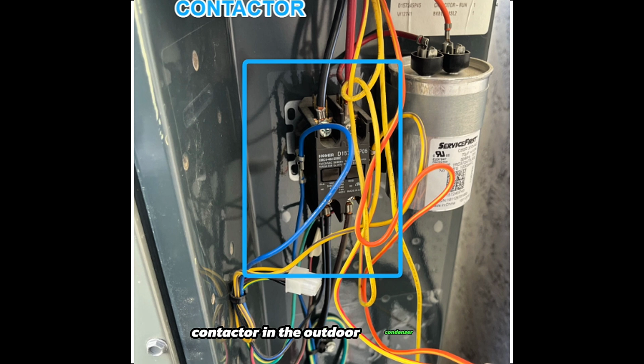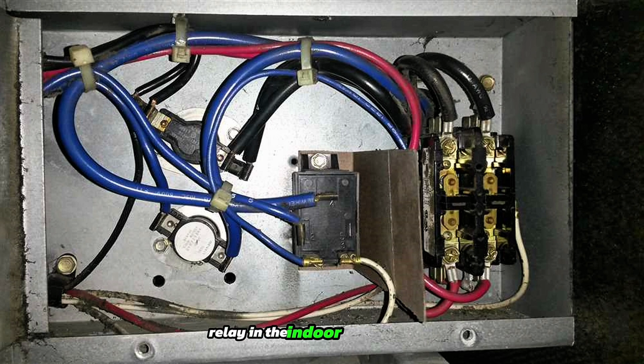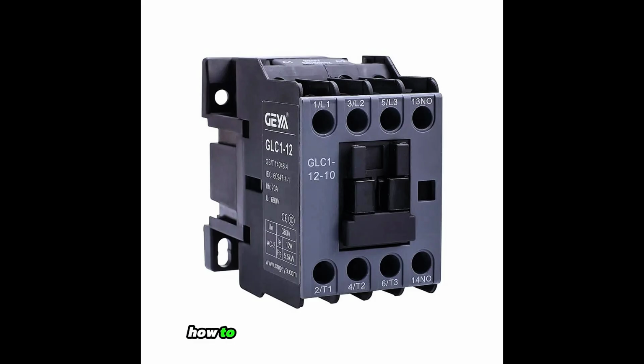Where you'll find them: a contactor in the outdoor condenser, switching the compressor and fan. A relay in the indoor air handler, switching the blower motor or electric heater. How to test a contactor, step by step: turn off power, always. Inspect the contacts. If they're pitted, blackened, or stuck, replace the contactor.